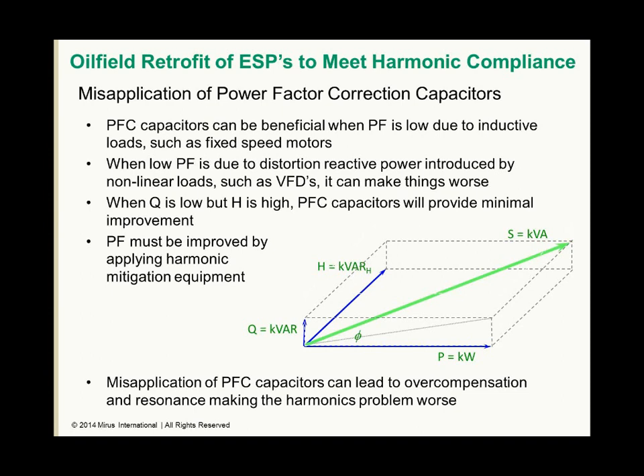For harmonic generating nonlinear loads such as VFDs, the Q component is usually very small, but the H component can be quite large. And it's that component that lowers the power factor. So improving power factor can only be achieved by mitigating the harmonics. Application of PFC capacitors will often make the problem worse.